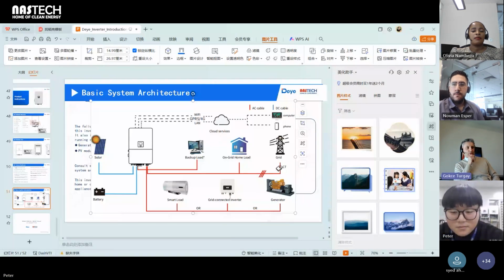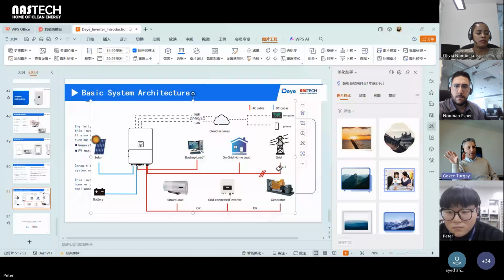Another question: how do you choose system voltage if the voltage ranges from 160 to 800 volt? I think for this particular guest, Naman, let's have a Teams meeting with Mr. Geoffrey. I think he has some fun, the principle of that low voltage, high voltage, how that voltage is changing and what is the effect on the system. Maybe we need to explain this in greater detail because this question is regarding the battery voltage side of the hybrid inverters. It doesn't have any effect on the load side or the PV side. So you don't select that voltage. It is a design criterion of the inverter itself.